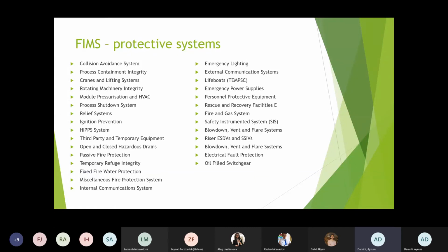Emergency lighting provides sufficient illumination for managing any incident and escape following loss of external power supply. And external communication systems provide reliable, direct, secure, essential and effective facilities for emergency external communication with other fixed or mobile installations, offshore installations, marine vessels, and neighboring shore-based facilities. Additionally, they ensure that prior to, during, and post-abandonment, the communications required for the emergency response control personnel mustering, platform evacuation, and with all external parties identified in the emergency plan are available.